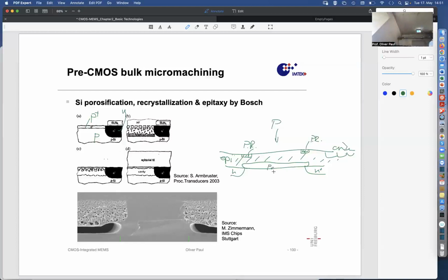The difference of the pressure will cause a response of the combination of these piezoresistors, if they are arranged appropriately on the surface of this membrane. And the membrane is not just a bridge, it's a real membrane with a cavity that may have a square or a round shape underneath, totally surrounded by silicon, a real enclosed cavity. So you can have any sensor geometry over a cavity by appropriately designing this N region definition, where the porosification will stop, not proceed. So it's a well-defined geometrical definition of the structure. So this is the basis of pressure sensors by Bosch, and of course Bosch makes a lot of money with that idea.